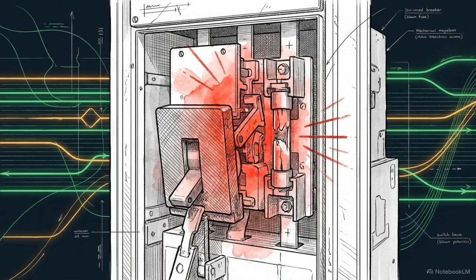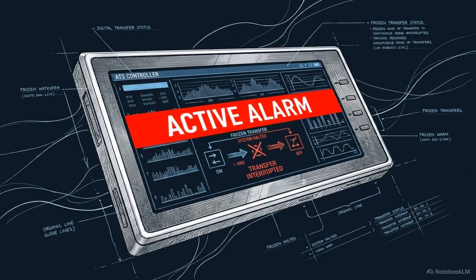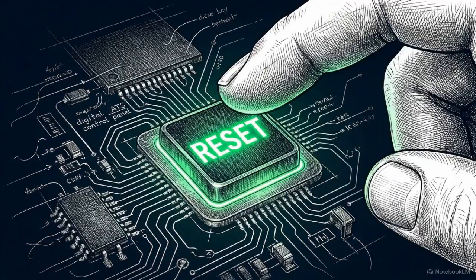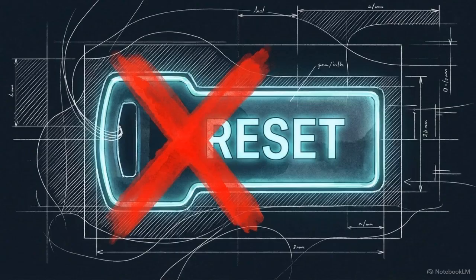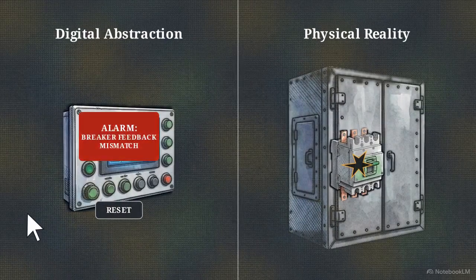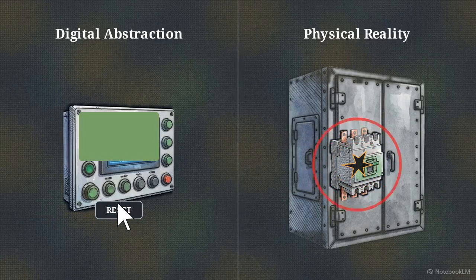During any of these sequences, a breaker mechanism might fail to move, causing the transfer logic to hang and triggering an active alarm state. There is a dangerous misconception that pressing the digital reset key on the controller is the primary method for clearing the fault. Pressing reset without investigating the physical switchgear merely clears the digital latch. The physical hazard remains active, drastically increasing the risk of a catastrophic system failure if the controller attempts another transfer.